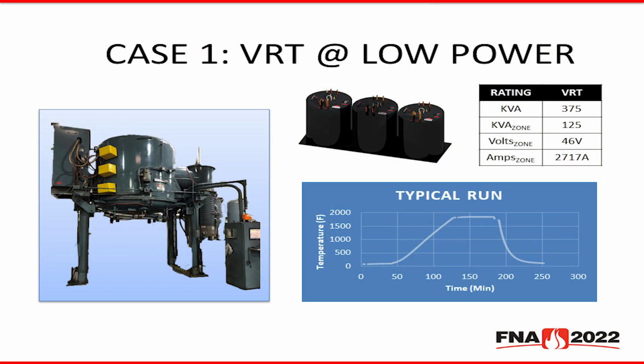So here is the first example of an electrically underperforming furnace. This case demonstrates why operation of a VRT at low power set points is electrically inefficient. This furnace is powered with a VRT rated at 375 kVA, which equates to 125 kVA per zone at 46 volts and 2,700 amps. So this cycle is also shown on the screen in blue.